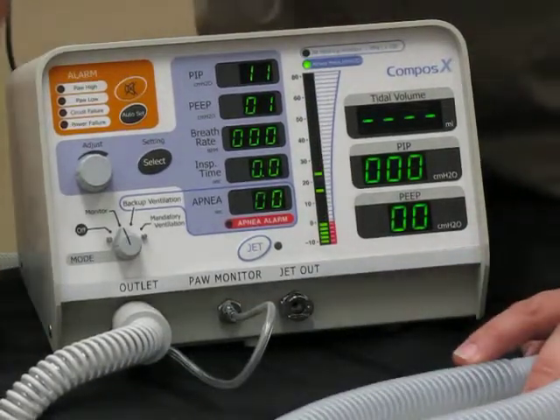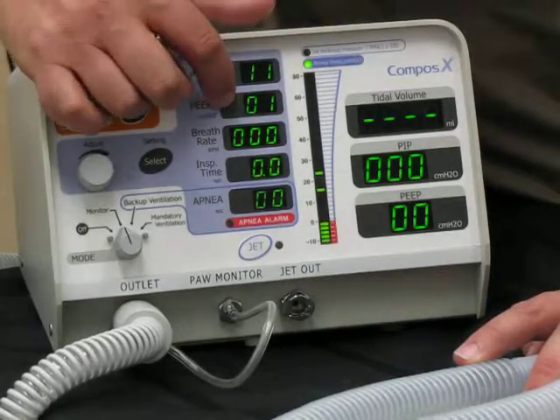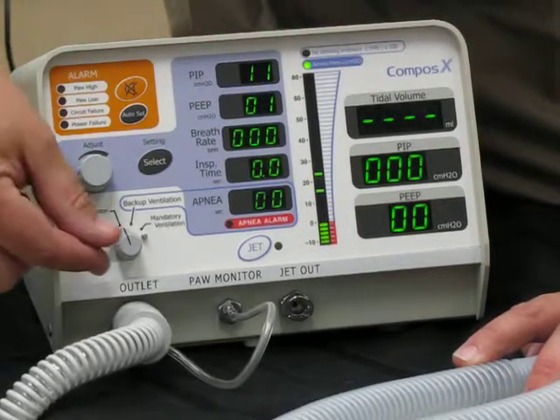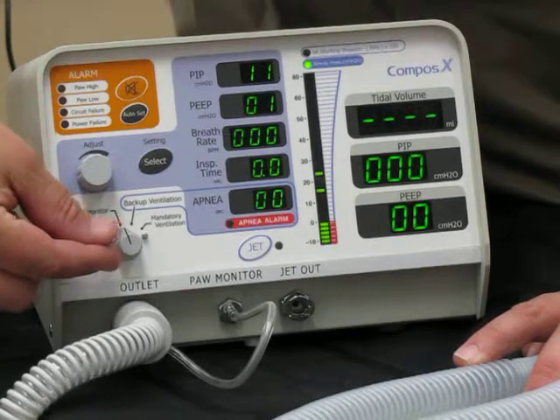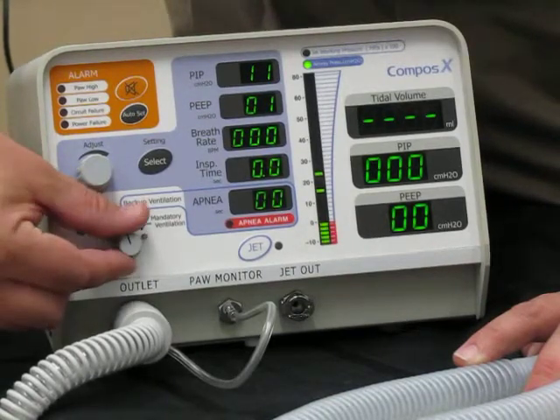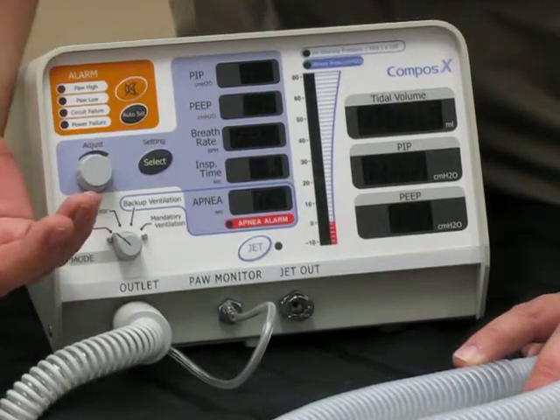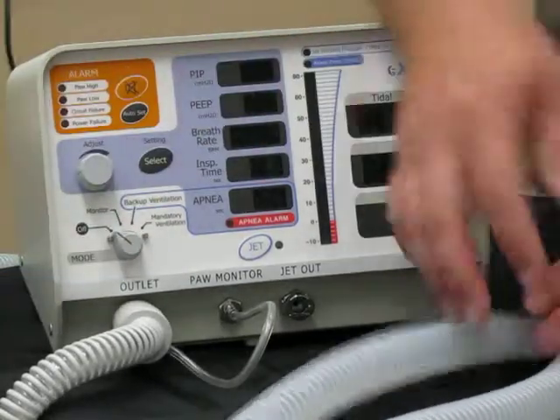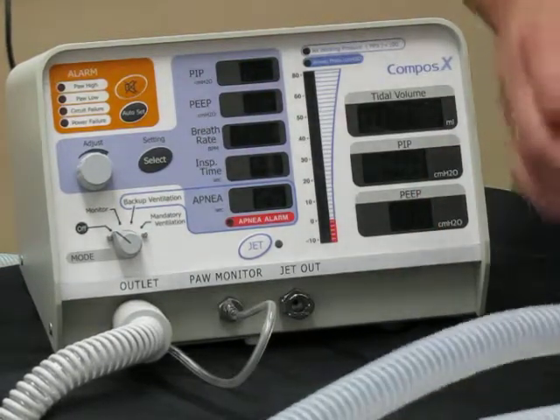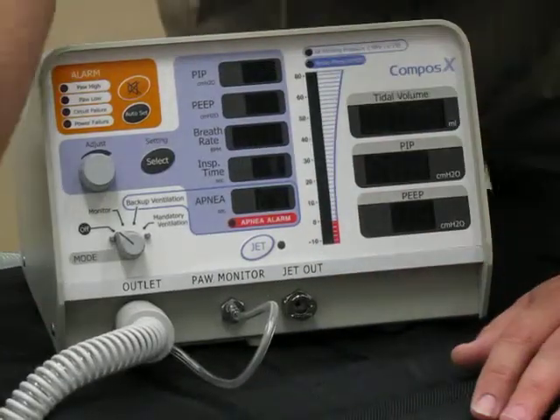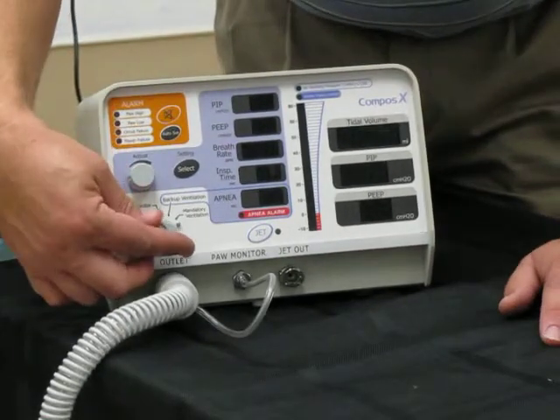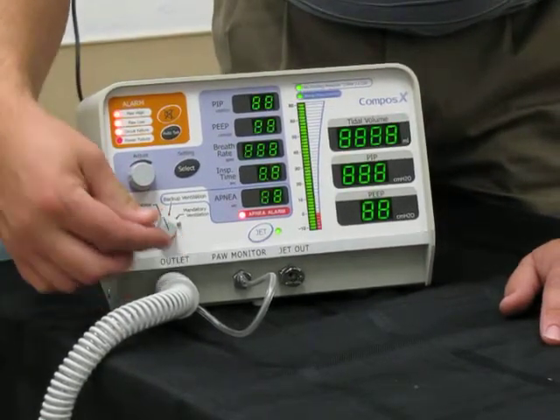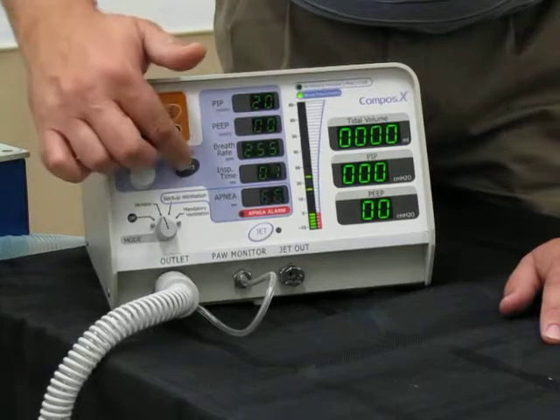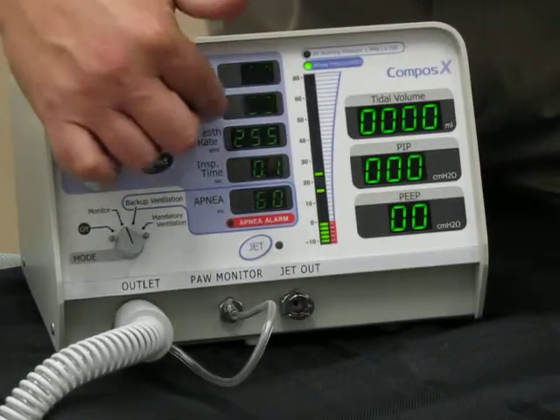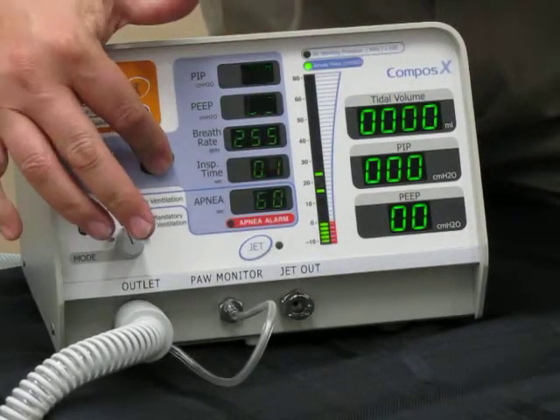Okay, it's finished its calibration. We've gone back to 1s, so everything's good. At this point I can turn the mode to off, which will take it out of its maintenance mode, and we can get ready to do the settings for our patient. So what we're going to do is just put it into a monitor mode, and to move between points on our settings, you just hit select.